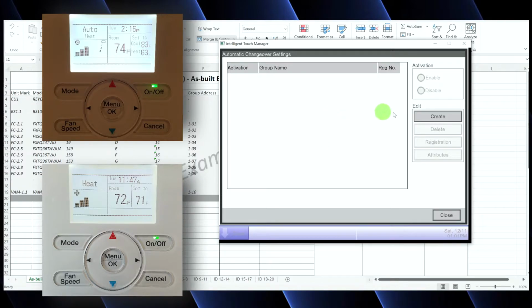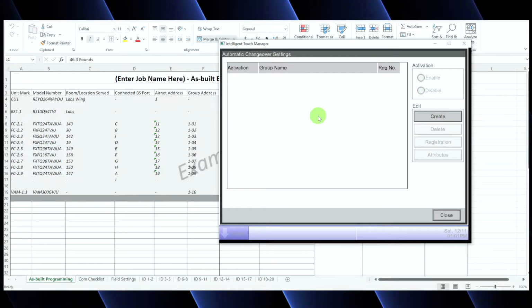So what you're going to do here is create an auto changeover parameter. You're going to set up how you want your units to change over from heating to cooling. Every now and then you're going to have an application where you may not want the ITM to handle the auto changeover. One of the examples would be a building that was a condominium. So you had all these condos, and technically every condo owner owned their indoor unit. You wouldn't have the ITM handling auto changeover. Instead, in this case you would set up the ITM as the slave. You wouldn't program in auto changeover, and then on all the nav controllers, you'd go in and basically re-enable schedule and auto changeover, so that way the thermostat had full control of its own zone.